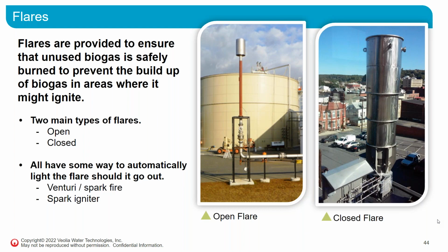combusted. It may also be common in situations like the plant in question here is in a downtown area, and the closed flare hides the flame from view, which could be a public concern for some folks. All flares, both open and closed, have some way to light the flare should it go out. This could be a venturi or a spark igniter. Most of them have an automatic relighting system, but some of them could require a manual relight.